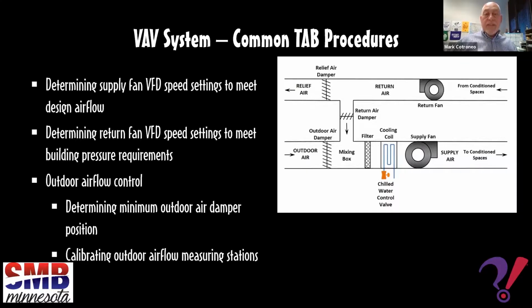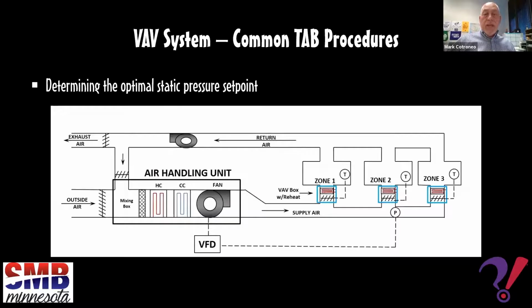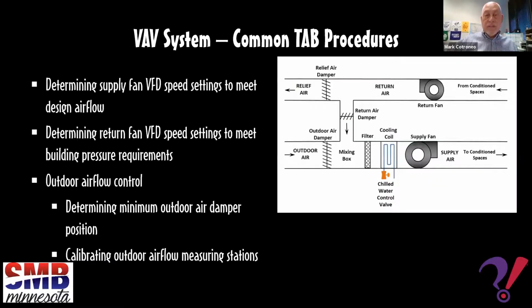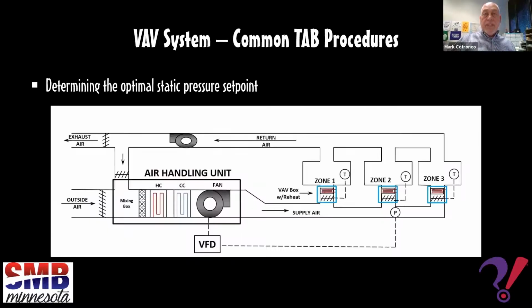The static set point in the system is set by monitoring the set point and the percent open of all the VAV boxes. By monitoring the BAS display, we're looking at all the VAV boxes, making sure that the boxes are all calling for some kind of cooling or open. Then the set point is adjusted up or down until only about 1 or 2 VAV boxes operate at 100% open position and are reading their design airflow.